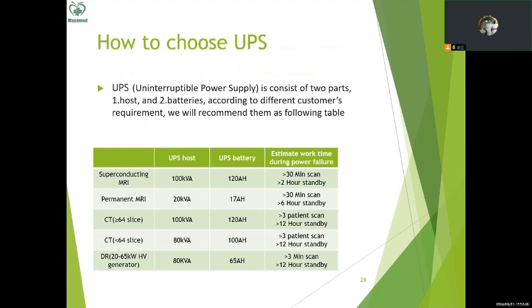For superconducting MRI, especially 1.5 Tesla, the UPS host should be at least 100 kVA. The UPS battery should be at least 120 Ah. If we use this configuration, the estimated work time during the power failure can sustain more than 30 minutes patient scan, or more than 2 hours system standby. For permanent MRI, the number is 20 kVA and 17 Ah, which is also available to support a 30-minute scan, and more than 6 hours standby.